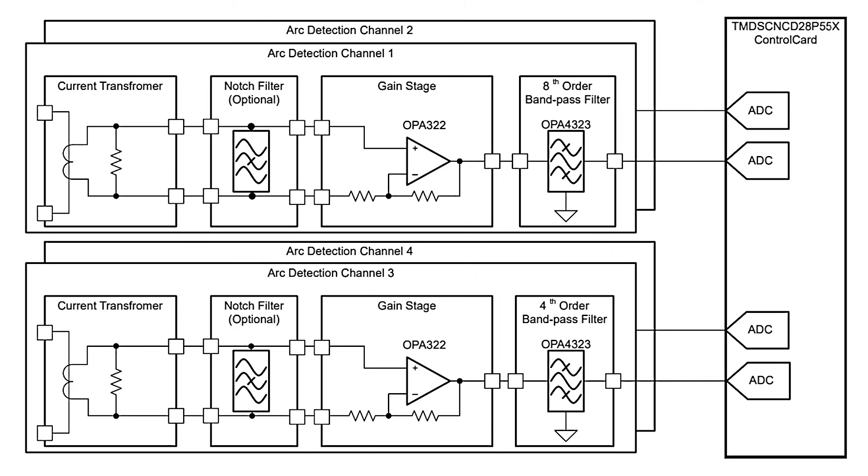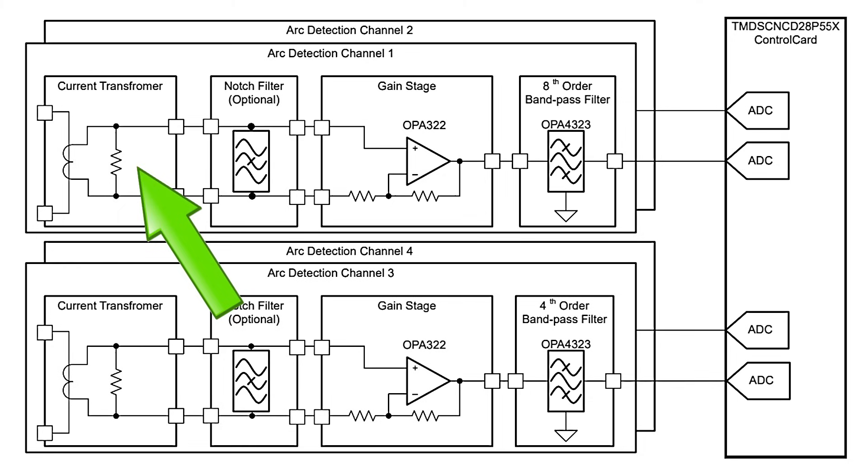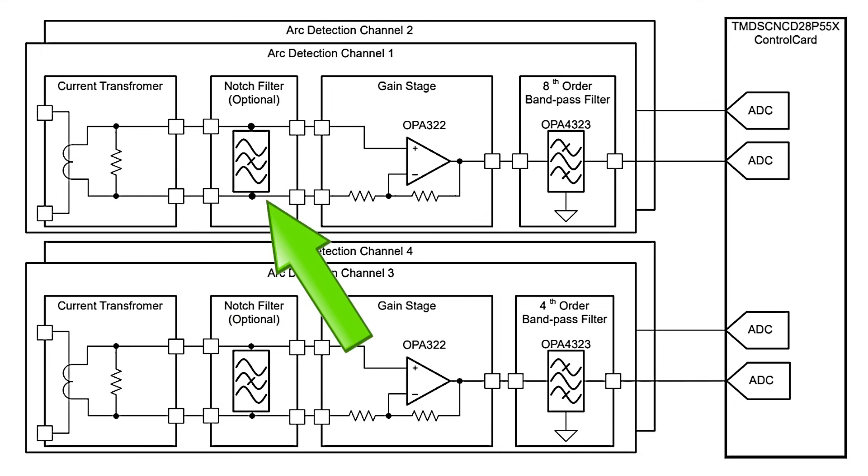One of the subsets included in the project consists of four independent analog front-end channels for arc detection. It includes four main blocks. Isolated current measurement through an integrated current transformer or connector for an external current sensor. Though the transformer is preferable for obvious isolation reasons.